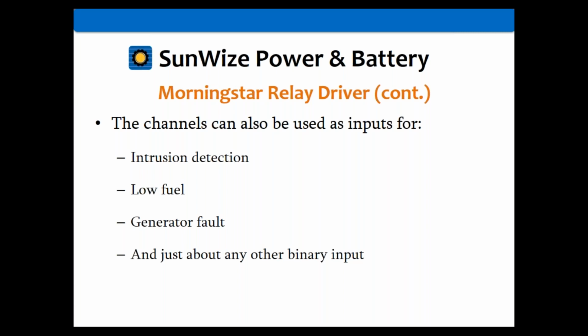You can get generator fault. This does generator control, so you can use one of the channels to turn the generator on and off, and use another channel to get feedback, since a lot of generators have a dry contact closure when there's a fault. You can get that back and communicate it remotely, sent through your Ethernet back to you saying, hey, I have a generator problem, so we need to go out and fix it. Just all kinds of things you can do with this, since it has a binary input, either on or off.